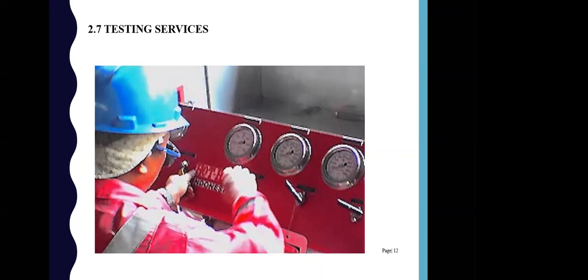To apply the test, it is the contractor's responsibility to provide all the testing equipment and tools, and to provide test procedures, a method statement for applying the test, indicating the procedures, the expected results, and the actual measures. The site inspectors and consultants have to verify the test. All tests should be witnessed and monitored by the supervision consultant.